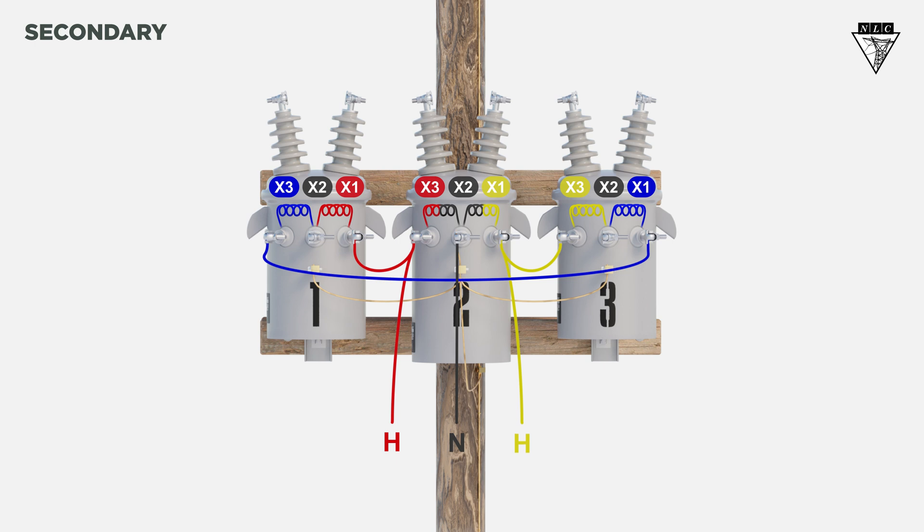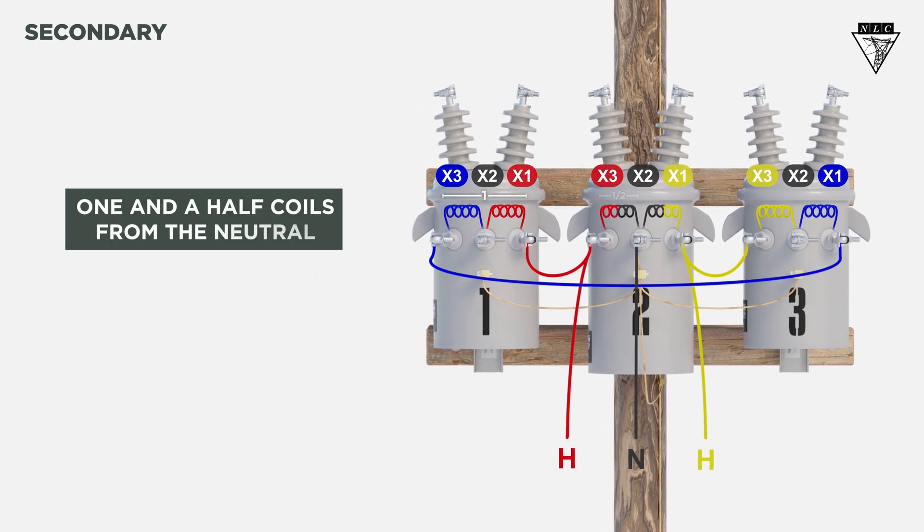The delta secondary will need a power leg to supply the three-phase load. The power leg is always placed one and a half coils from the neutral. In this example, we'll use the X3 on the first transformer, which we'll refer to as the power transformer. Remember, the power leg differs from the hot legs and should never be used to supply single-phase power. It's reserved for three-phase power only.